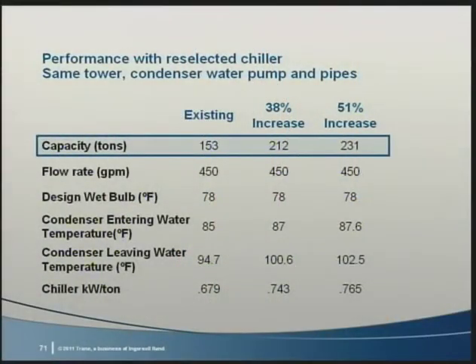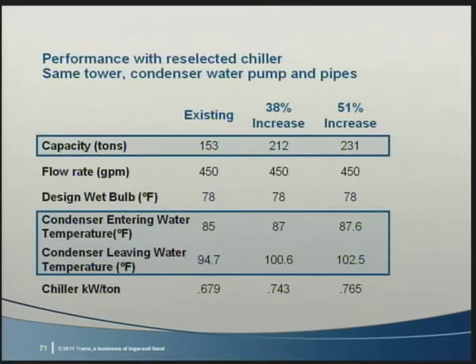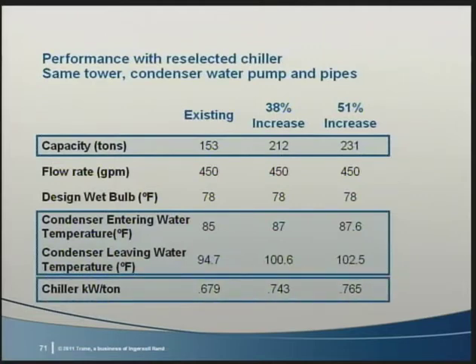But there's no free lunch. First, at each step, the chiller is physically larger. Next, you notice that the cooling tower can reject the heat, but the result is higher condenser entering and leaving water temperatures. However, since the chillers are newer, they're more efficient than the 20-year-old chiller, even at the raised condenser conditions. Using the existing pipes, pump, and cooling tower may well bring the job back into budget and allow it to move forward.